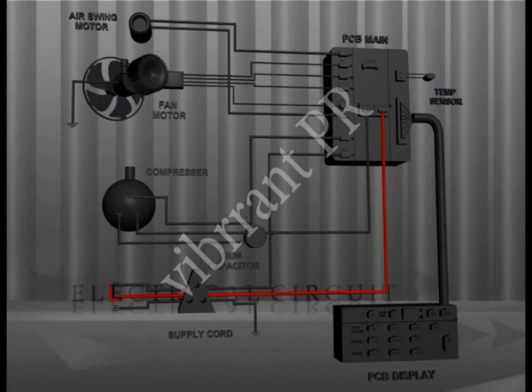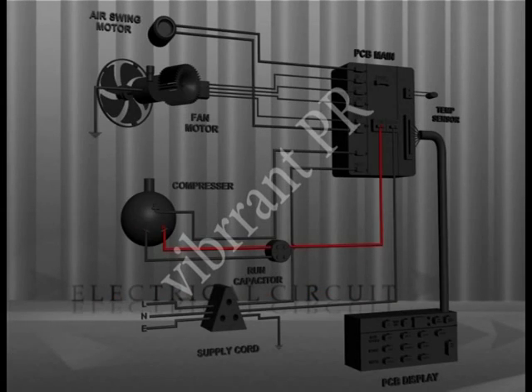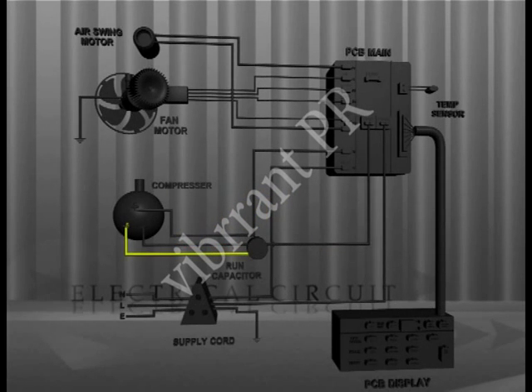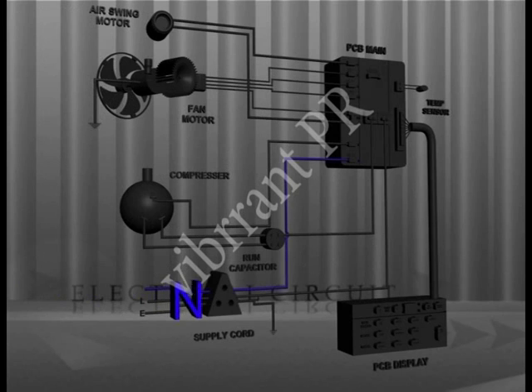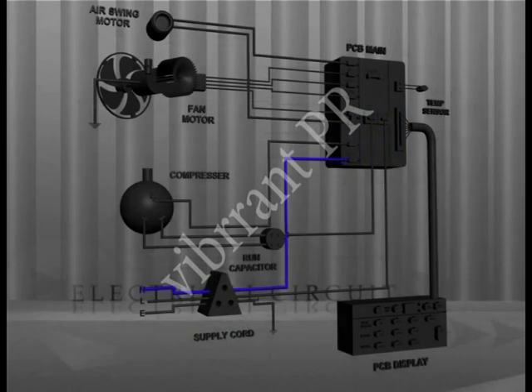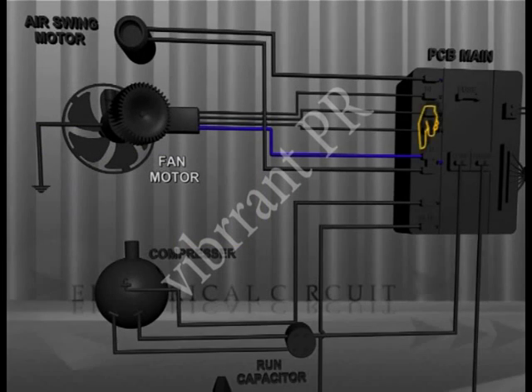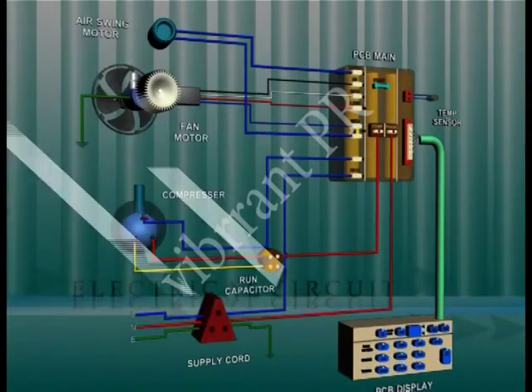The live wire L goes to terminal 3 of the relay in the PCB main. The live wire returns from relay terminal 4 to the running terminal R of the compressor through the run capacitor. The yellow wire from the run capacitor goes into the starting terminal S of the compressor. The neutral wire N goes to PCB main terminal P7 and returns from terminal P6 to the common terminal C of the compressor. The supply goes to the fan motor from the inbuilt connections of the main PCB.